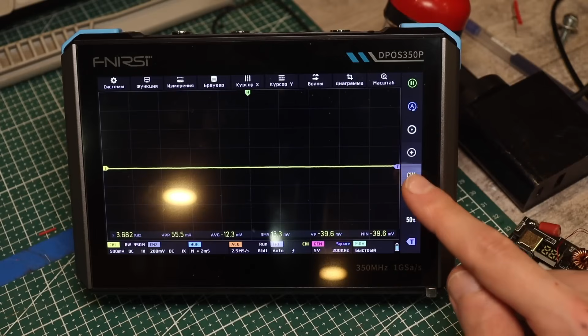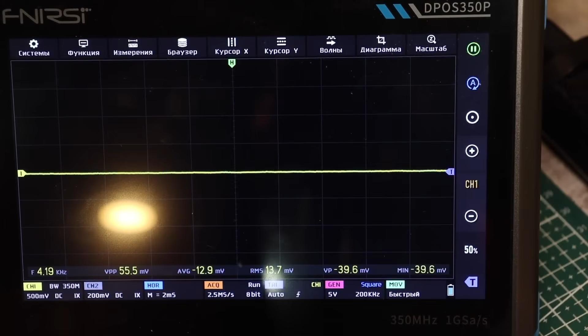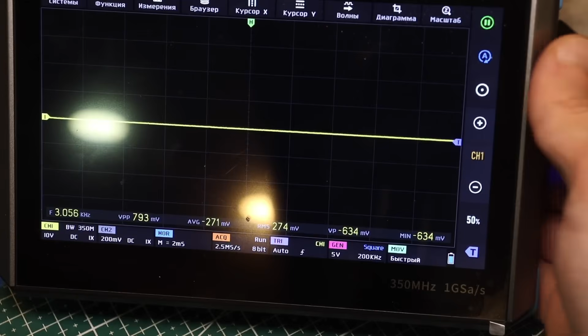We also select the channel depending on which channel we want to make these changes for. Well, in this case, let's use the first channel. Take a look here. It might seem that when we press the plus button, we're increasing the voltage, or more precisely, the value per division on the vertical scale, and accordingly, pressing minus decreases it. But actually the opposite happens. Alright, let me try to focus now. Here, look, it says 500 millivolts, right? We press the plus button and it actually decreases, and vice versa. So it's not really set up the way it should be. Maybe the manufacturer had their own reasons, or it's just a mistake. Or maybe I'm missing something, I don't know.